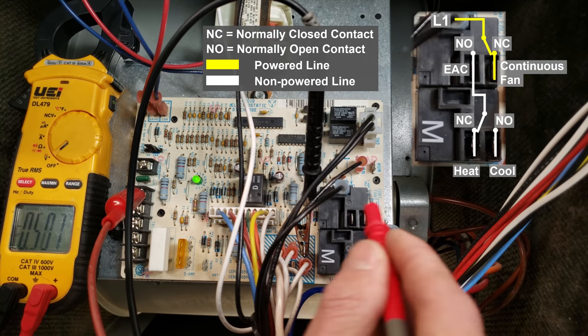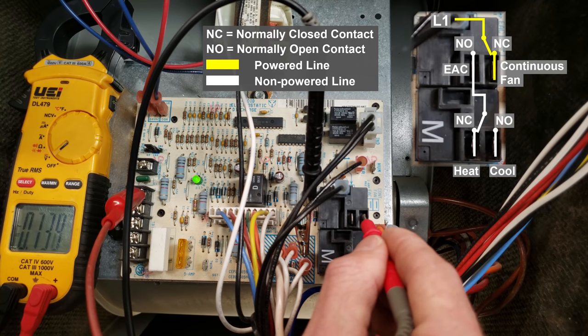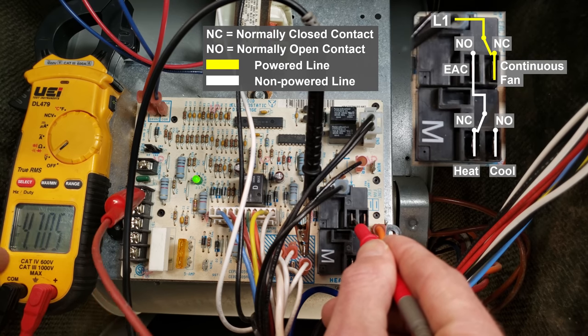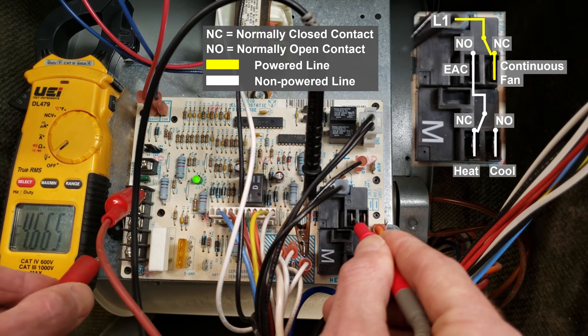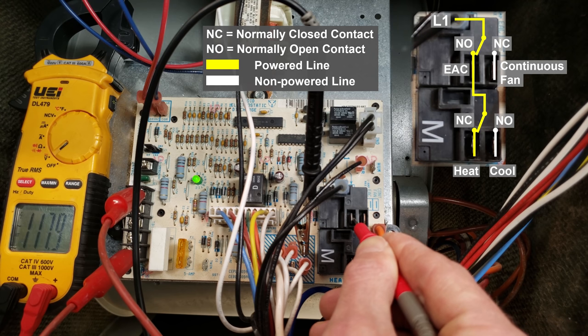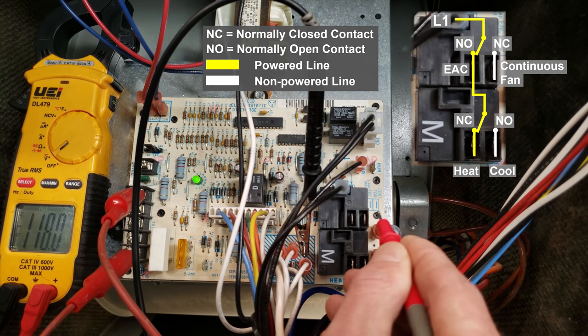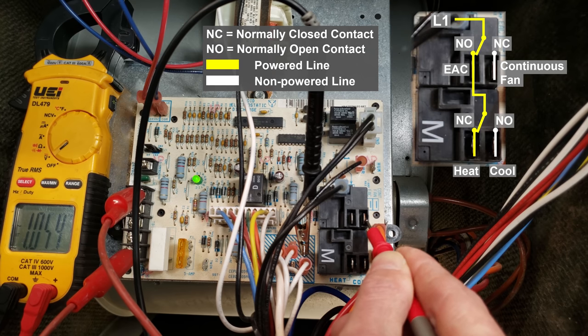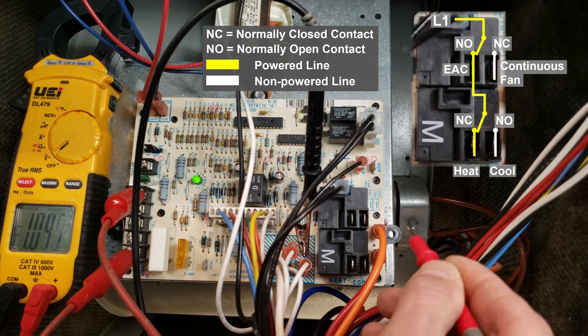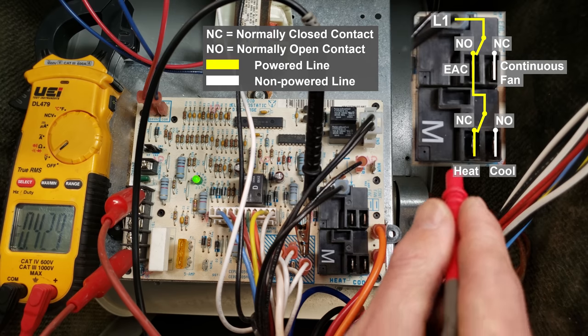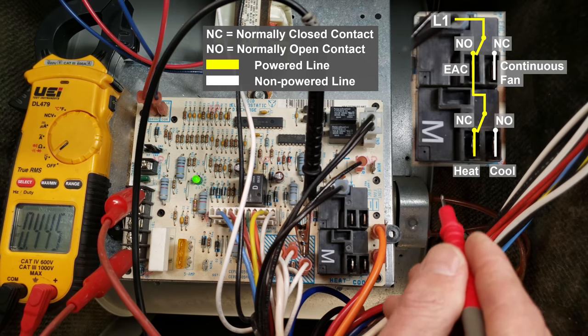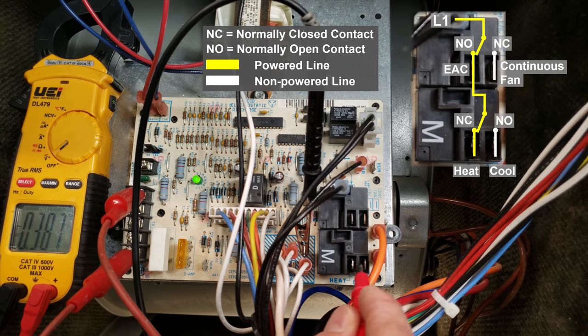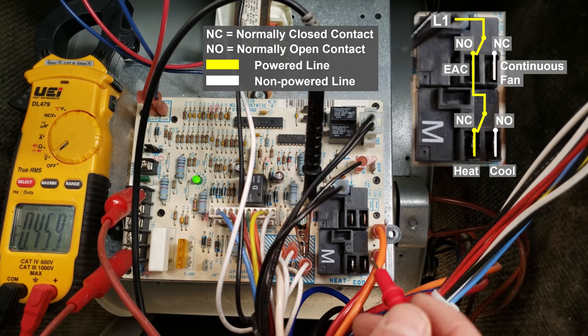Let's put it on the EAC, you see we have no power, we're measuring 4.7 volts. Let's connect over to G and now you see we have 118 volts over here and we have nothing on the continuous fan. So if you had one of these speeds connected to the continuous fan, that blower motor would run anytime this furnace had power except for when you're calling heat or cooling to turn on, and then it would run on the designated speed down here.